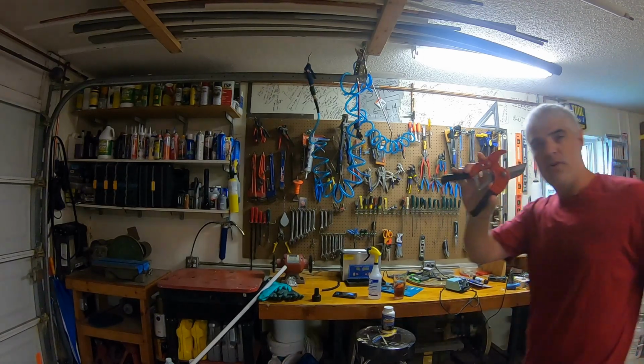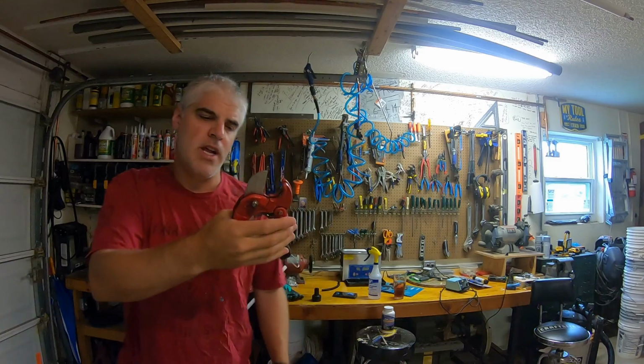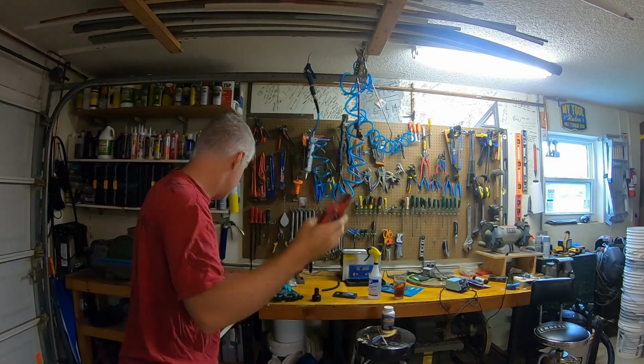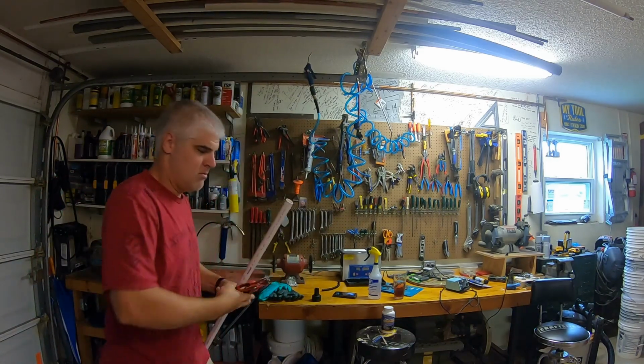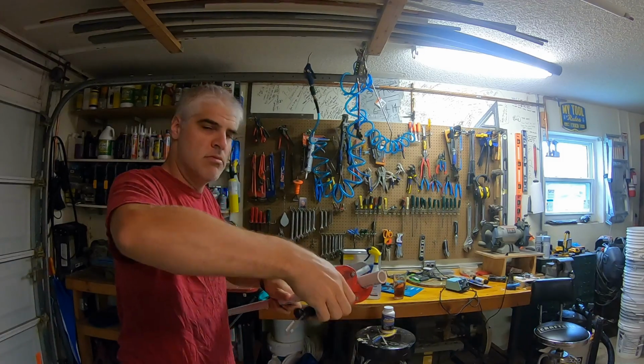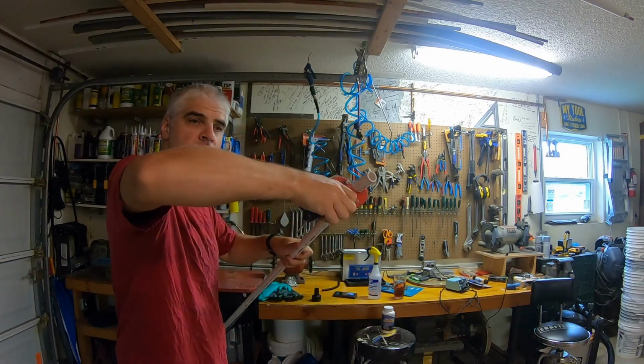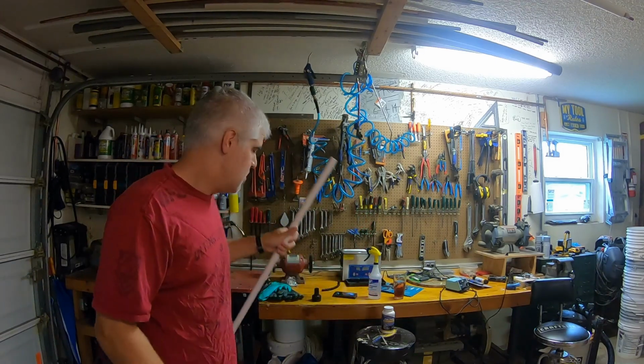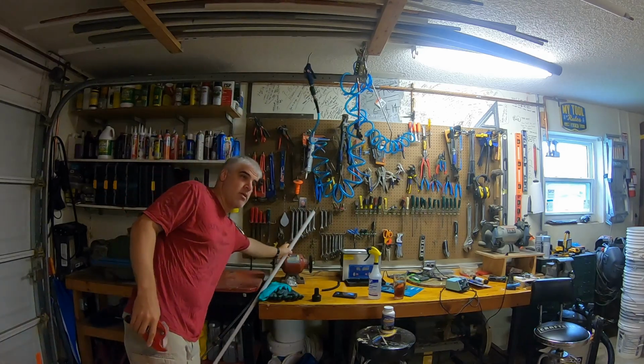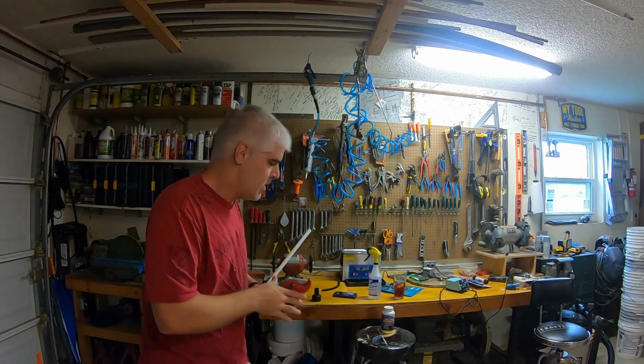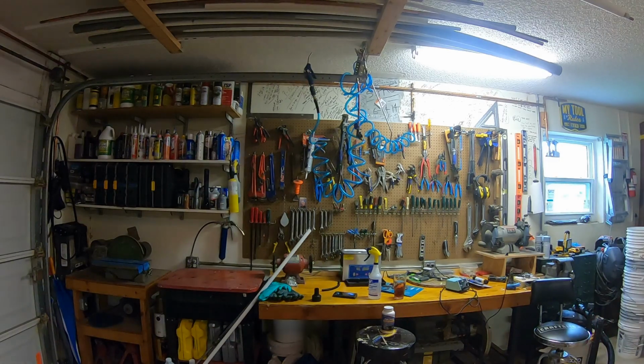So they look like these. You can also pick these up at home centers. You'll find them in the sprinkler aisle or in the PVC aisle, but they're just ratcheting cutters. So they'll cut a piece off the pipe in your attic or in your garage, wherever your air handler may be, and they will plug an adapter into that, and they will blow dry nitrogen through it.